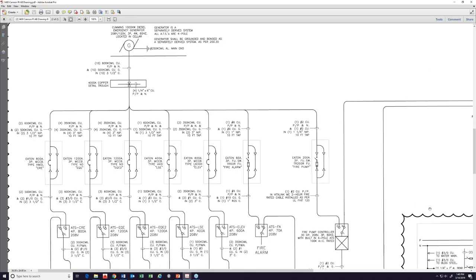Here's another one that's kind of a follow-up to this. It says, if the AHJs and utilities require a visible disconnect between the generator and the load served by the utility, is a generator output breaker required in that case? Yeah, in some places that is true. But it doesn't have to have an overcurrent protective device. It can be a simple disconnect. So you can put an unfused switch, or you can use basically a circuit breaker that does not have a trip unit, and it's simply a molded case switch.